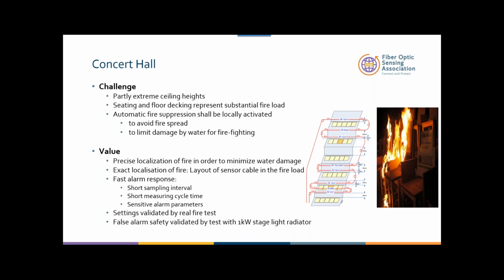We also have done, in my opinion, one of the coolest projects, a concert hall. This concert hall is very challenging in the sense that you can go to an opera house, one of the most prestigious opera houses in Europe, and the ability to pinpoint exactly, because the ceilings are too high, where the fire could be coming from, and flood that particular area, is extremely important. The challenges are, you want to avoid the fire spreading. You have about 500 people in the room, and you want to limit the water damage as well, because when you're flooding the area, you can do a lot of water damage.